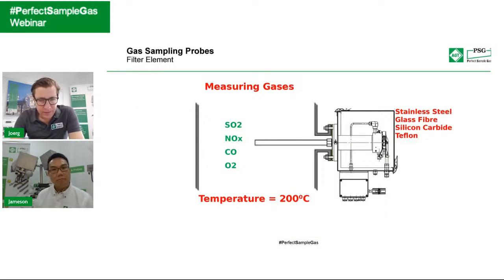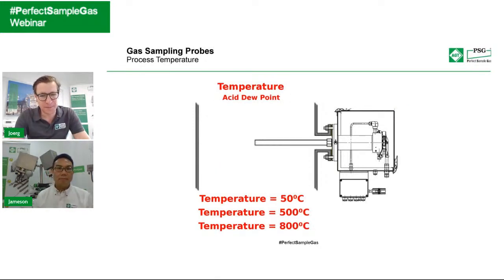Maybe, I think that's already something you started to mention here, Jemson, the different components and the acid dew point. Obviously, the components in or for the gas sampling probes are important. That this is stainless steel, and depending on what kind of measurement you have to choose the right filter material, right? And this is also something in our system with our probes. You don't even need any tools. You can do it without tools. You would be able to change the filter element itself, so that should be fine.